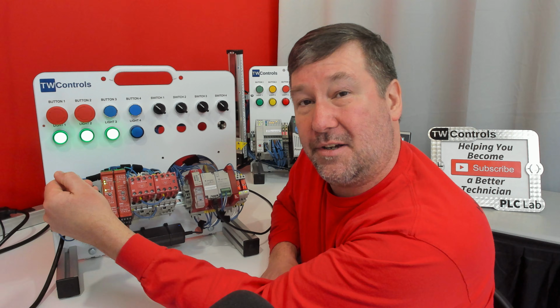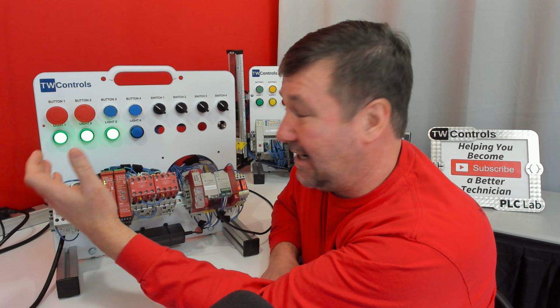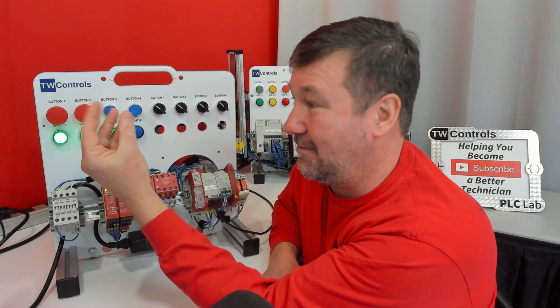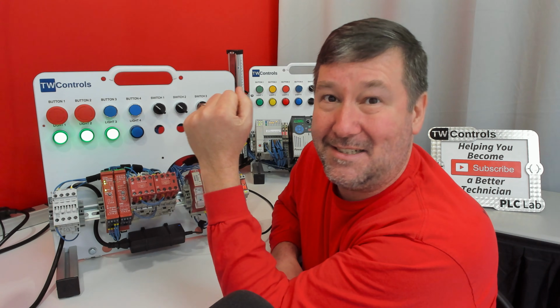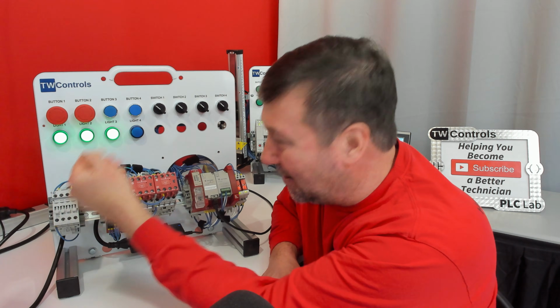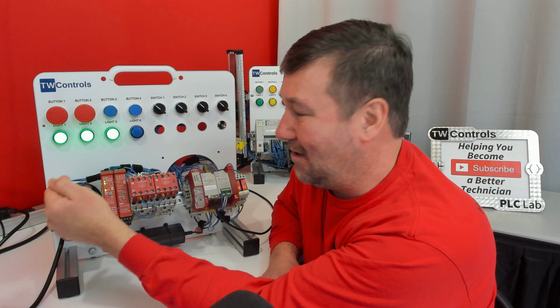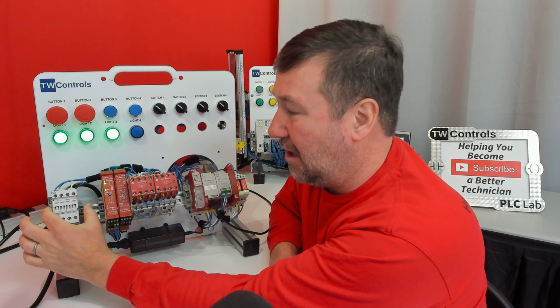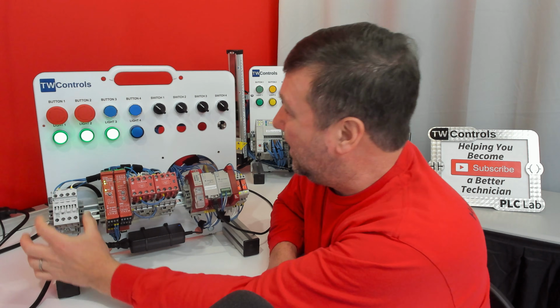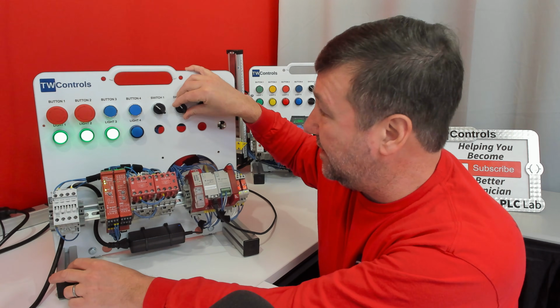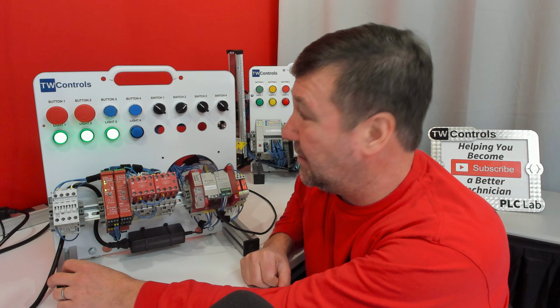Well, as you overload a contactor, you're going to heat up those contacts. And as you heat up those contacts, eventually they'll melt. And yes, we're usually building that heat while a contact is energized, which means we have a high probability of a welded contact here. And so switch 2 simulates a welded contact.